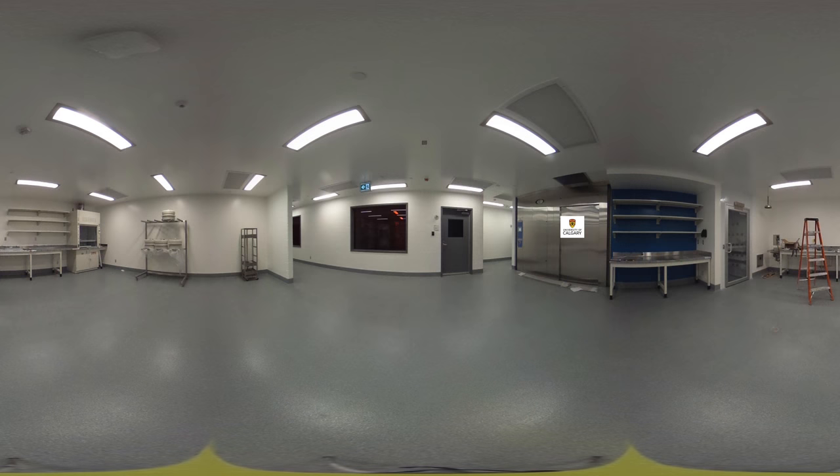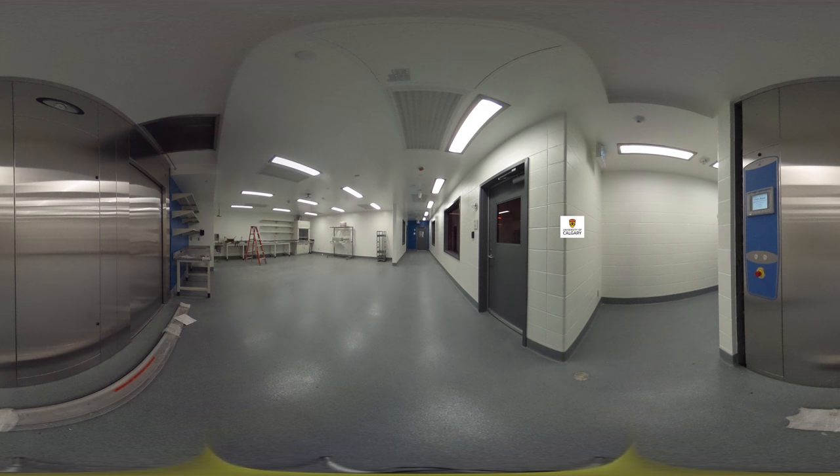This is a large room where we do a lot of the work. On the wall here is a large bulk autoclave, and any material that needs to enter this facility has to be autoclaved in. An autoclave is like a massive pressure cooker — all material gets put into sealed drums and then put into the autoclave. It's entered on the dirty side, and when it's done, this door opens and you can bring all of your sterile material in here to the clean side.